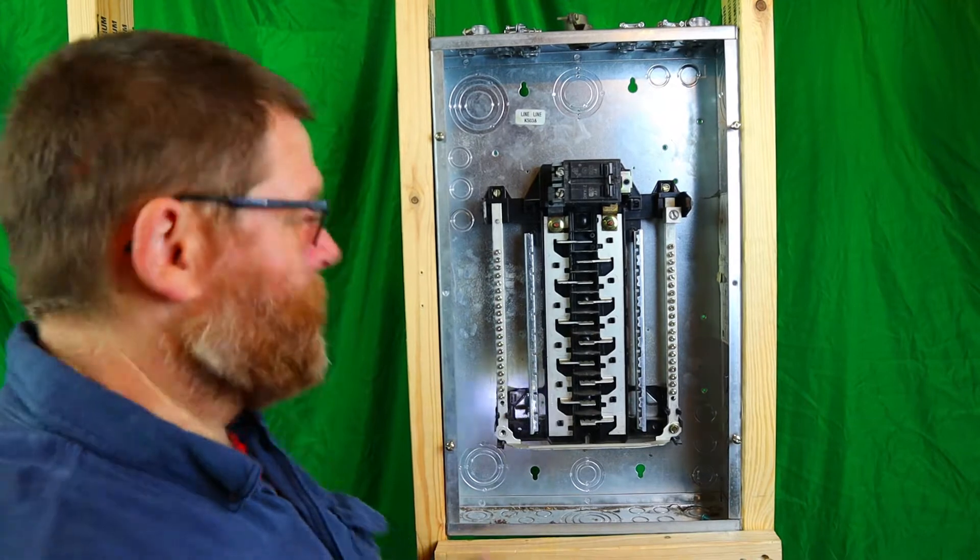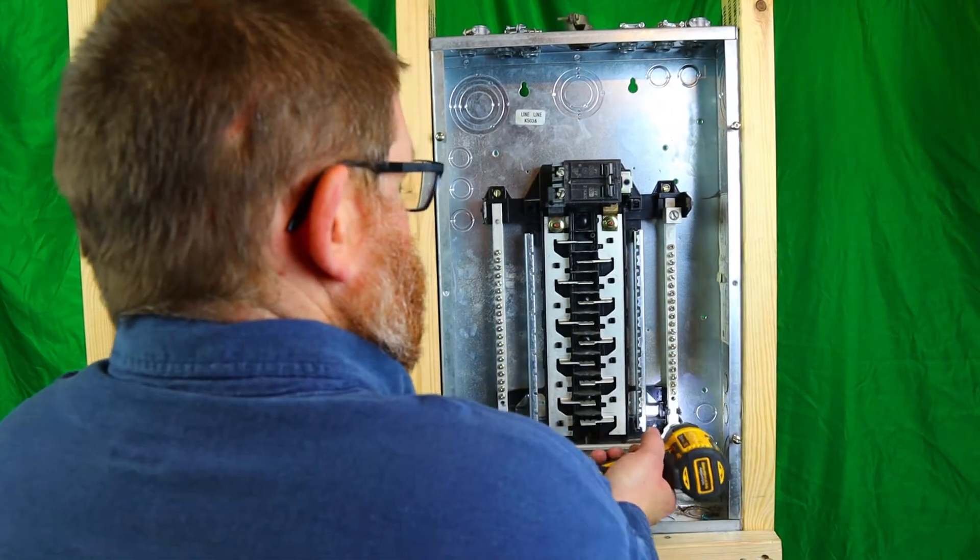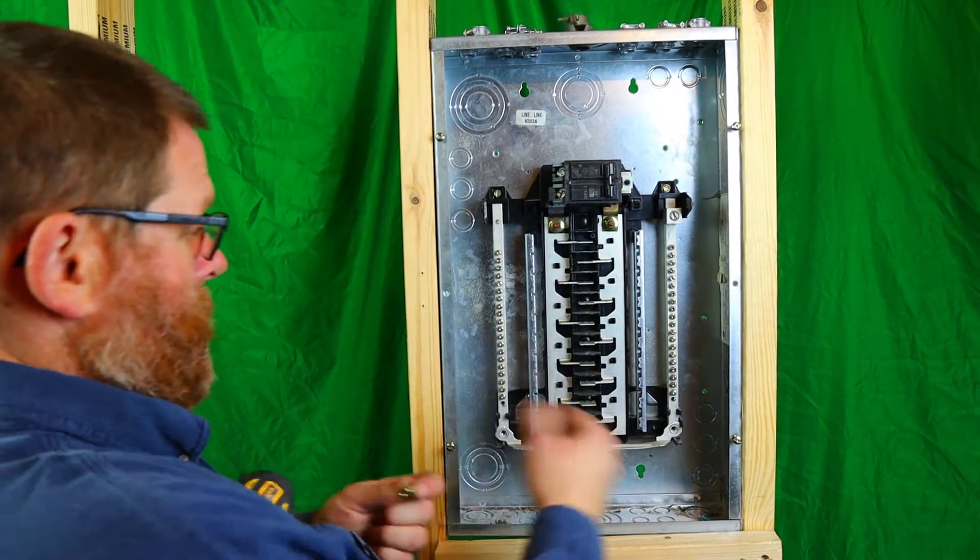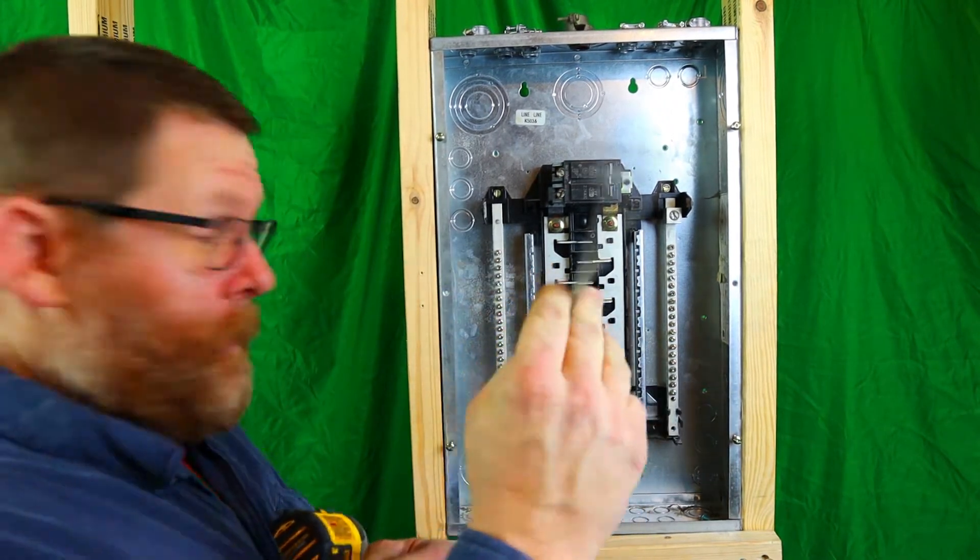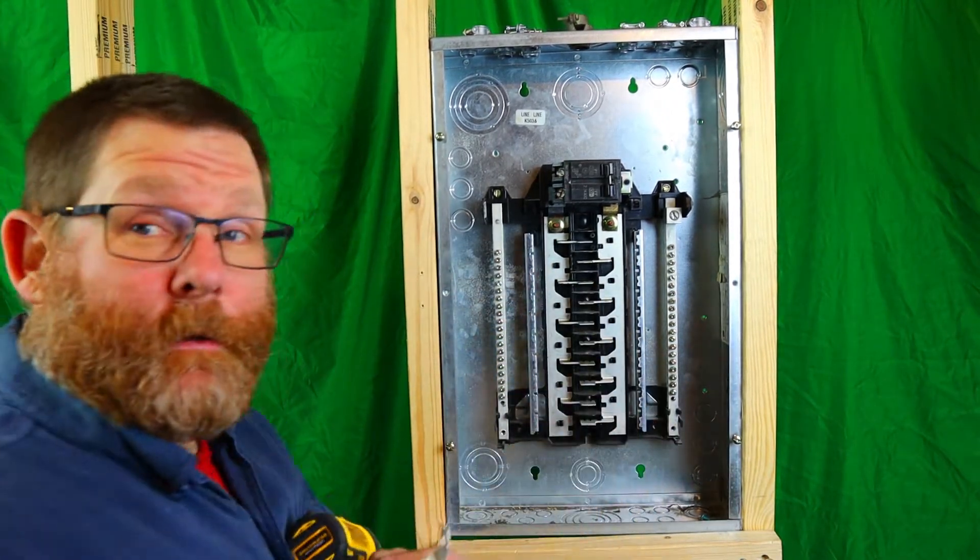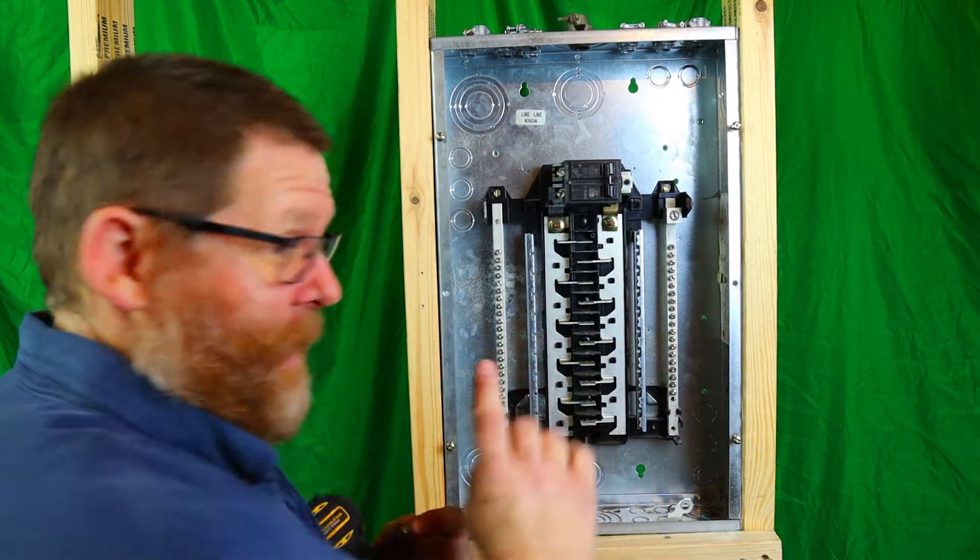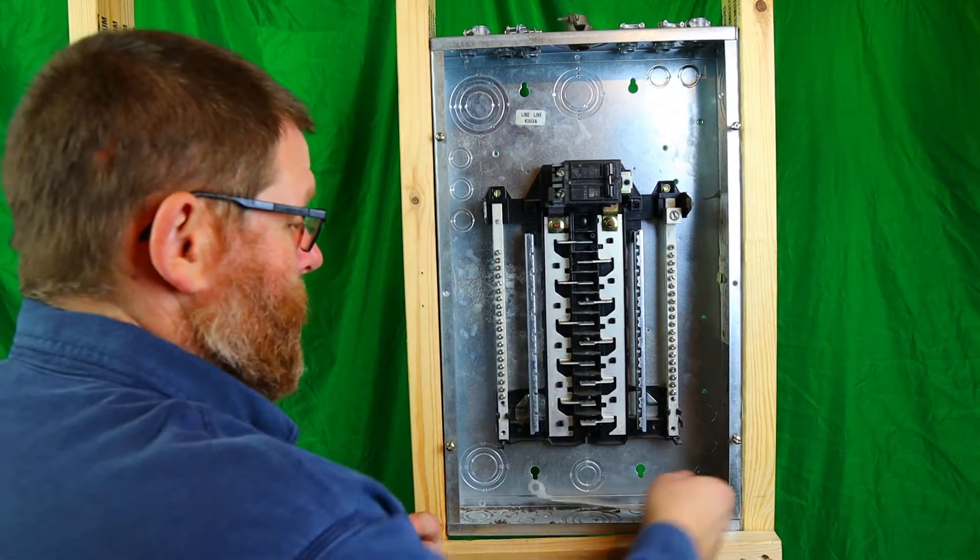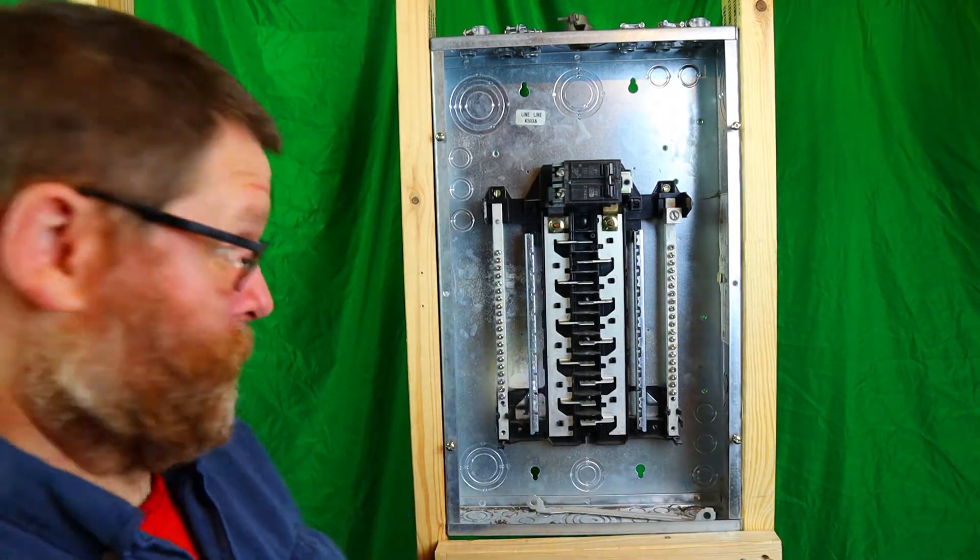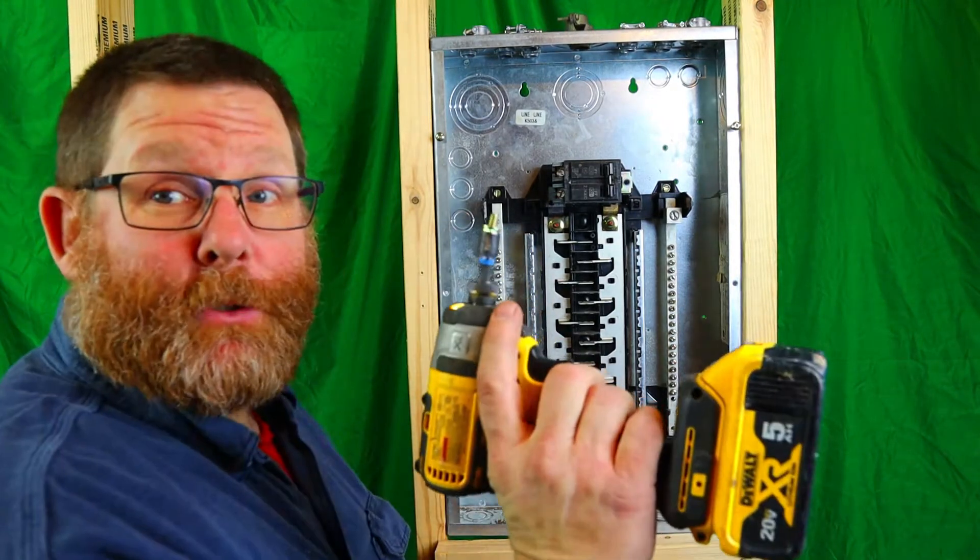Now these are three-eighths screws - I'm going to use an impact, take it off. Excuse me, they're three-eighths bolts. We're going to take the bar off. Now they're separated. That is very important. Do not throw this bar away at all, because one day you may have to use this panel for something else. You want to put the screws back in.